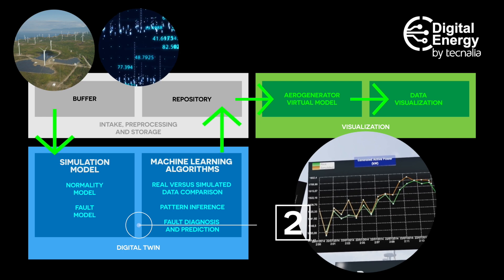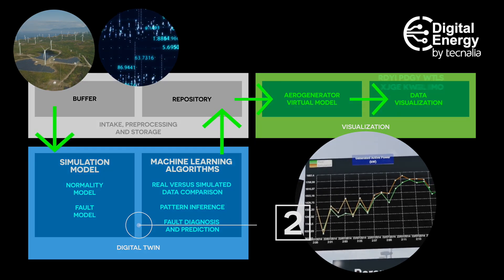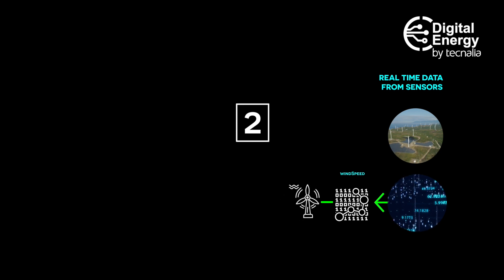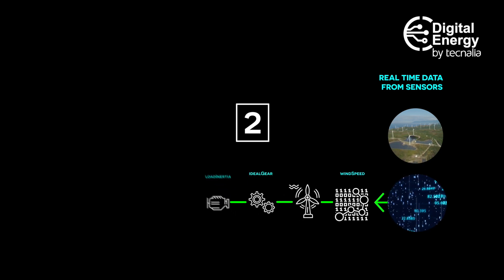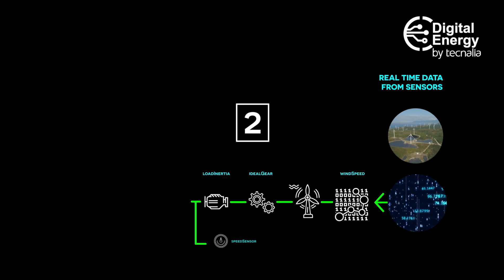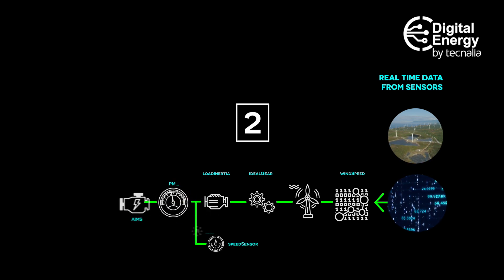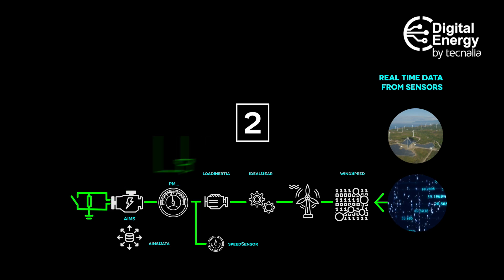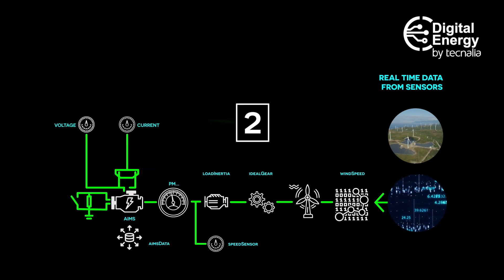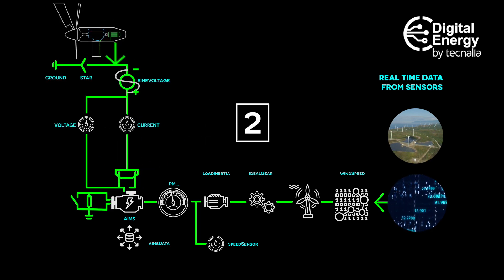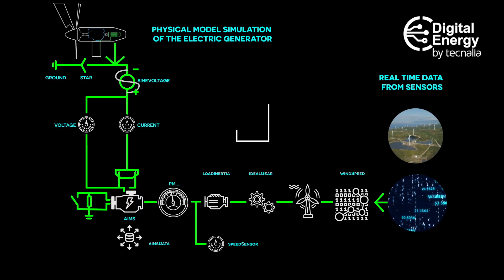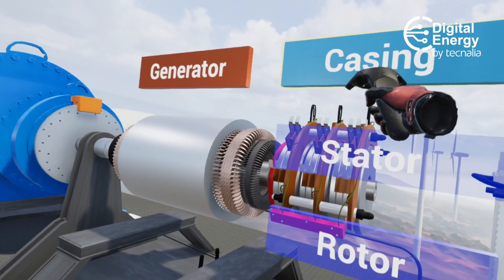Secondly, the digital twin of the electric generator, which integrates a physical-based model that simulates the behaviour of the asset in both normal and failure conditions, supported by machine learning algorithms that analyze the similarities and differences between simulated and real values in order to diagnose the health of the asset, predict future failures and estimate the remaining useful life.